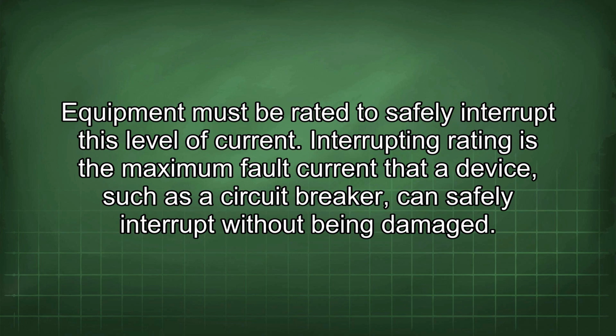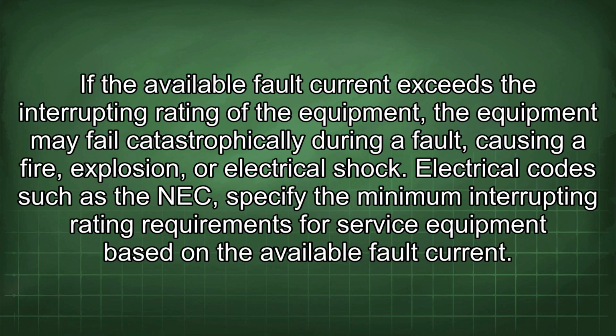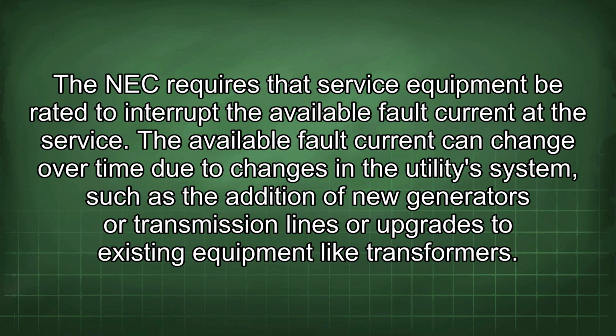Interrupting rating is the maximum fault current that a device, such as a circuit breaker, can safely interrupt without being damaged. If the available fault current exceeds the interrupting rating, the equipment may fail catastrophically during a fault, causing a fire, explosion, or electrical shock. Electrical codes such as the NEC specify the minimum interrupting rating requirements for service equipment based on the available fault current. The NEC requires that service equipment be rated to interrupt the available fault current at the service.